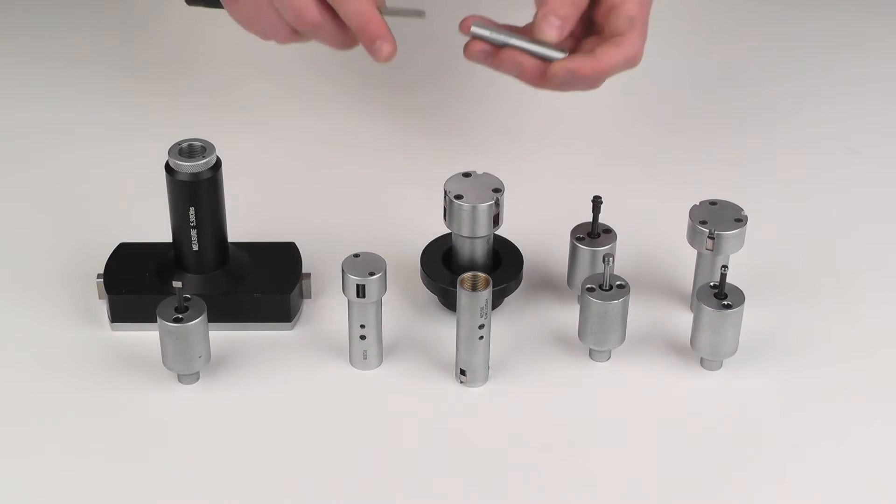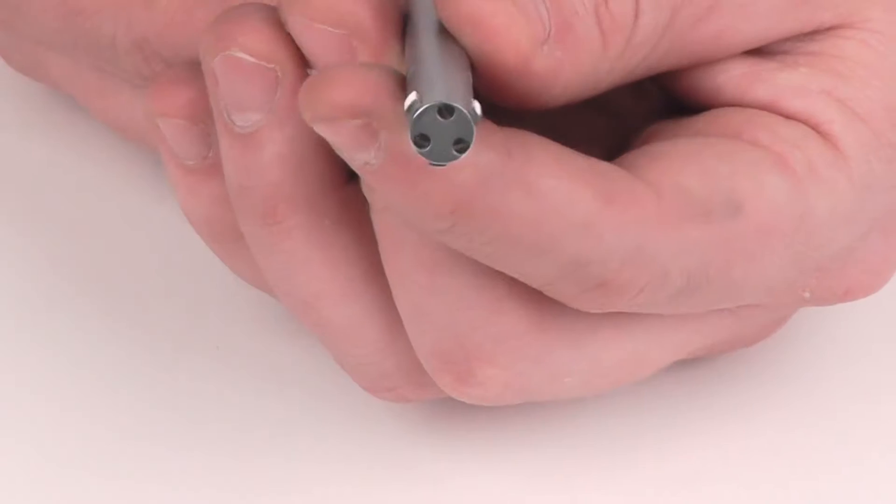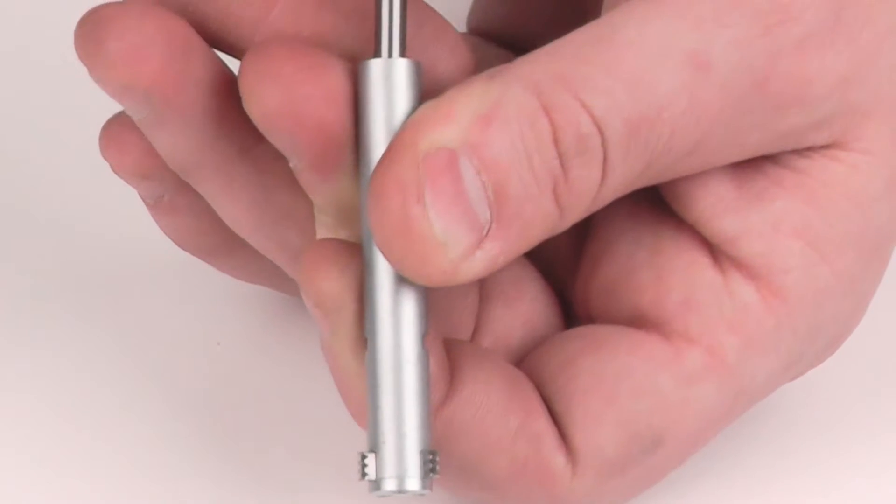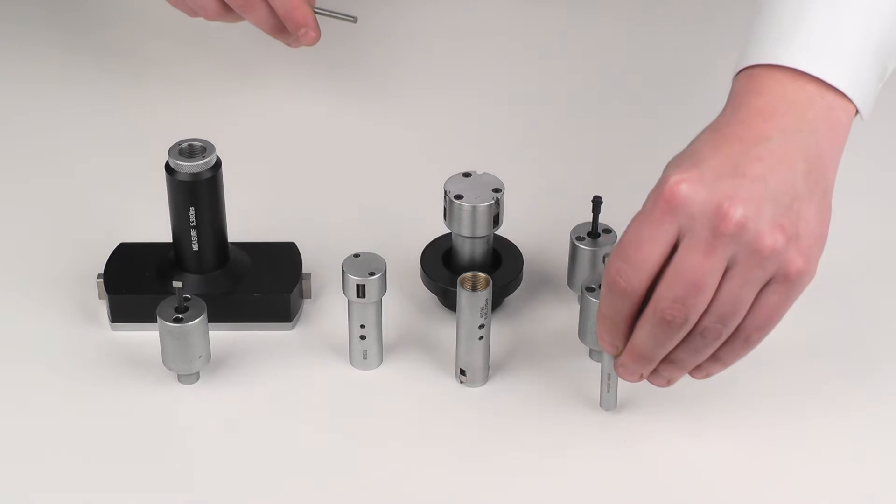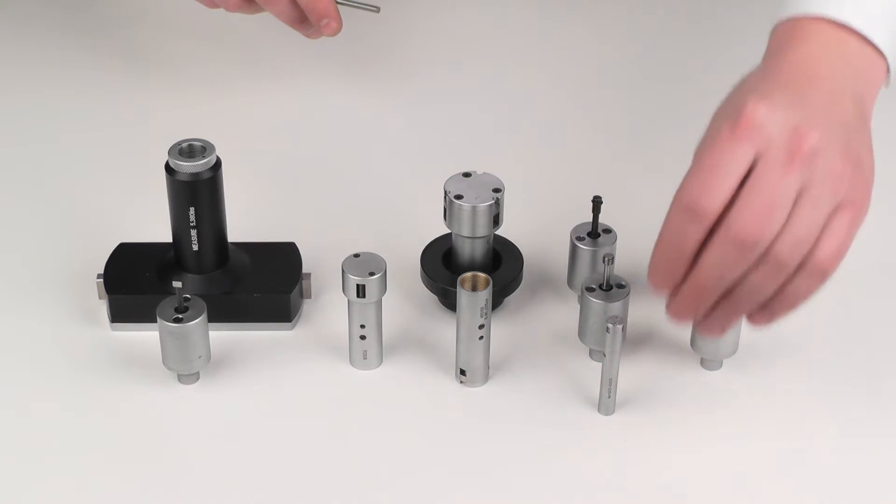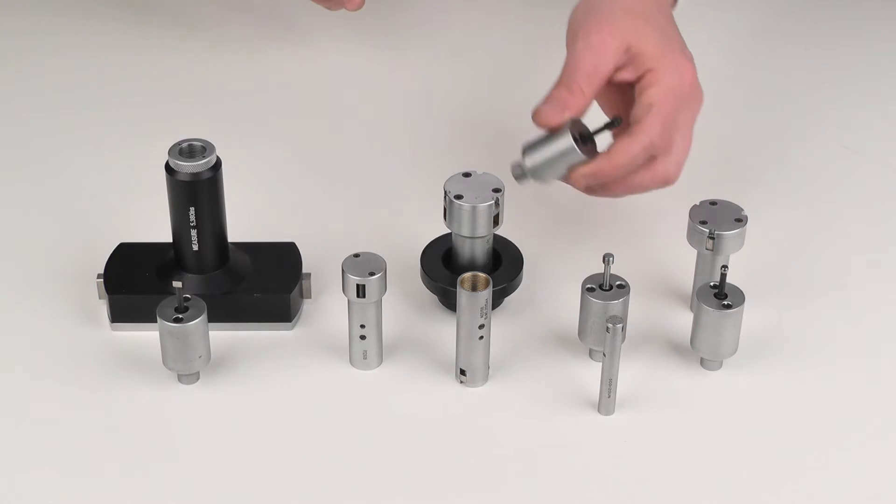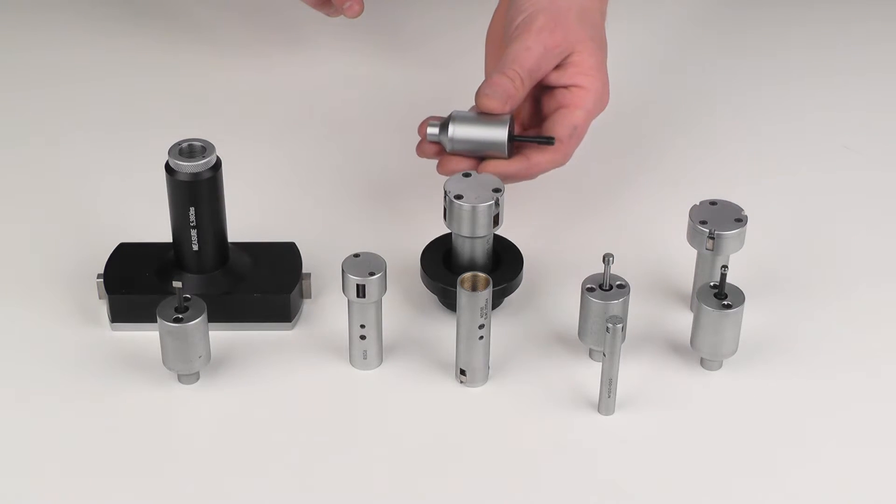For the thread measuring system, there is the possibility of having a multi-point measurement, or if a closer look is intended for the pitch diameter of a single thread, it can be cut with just a single thread as well.